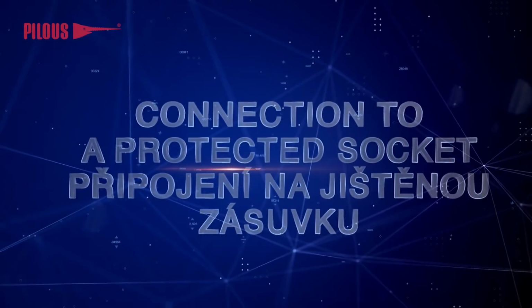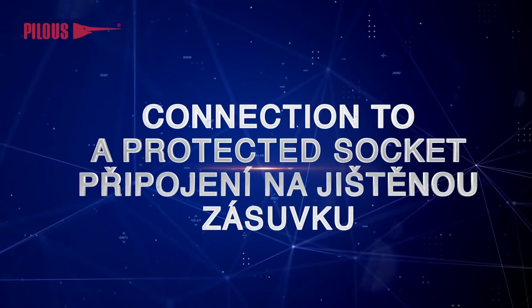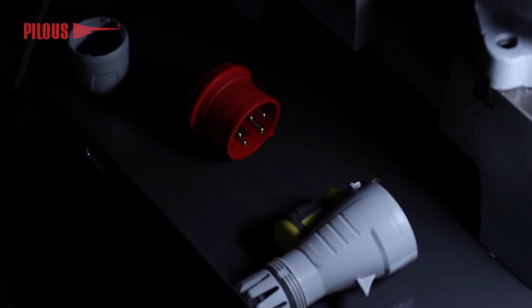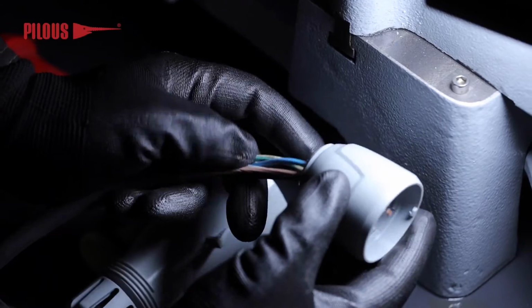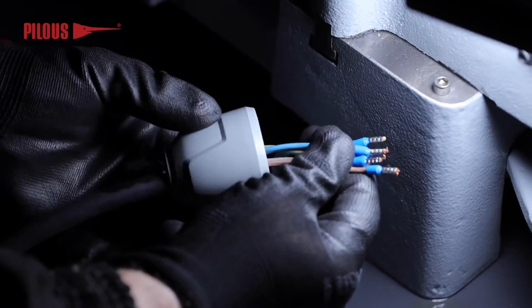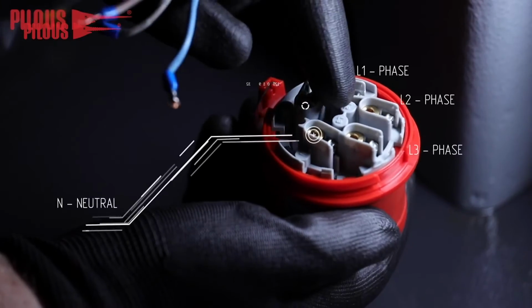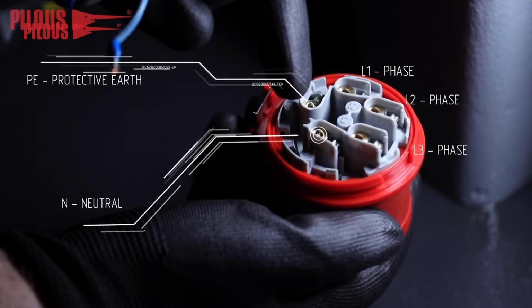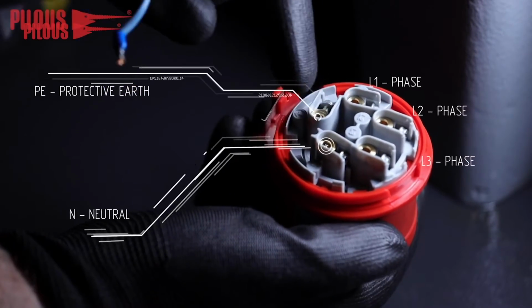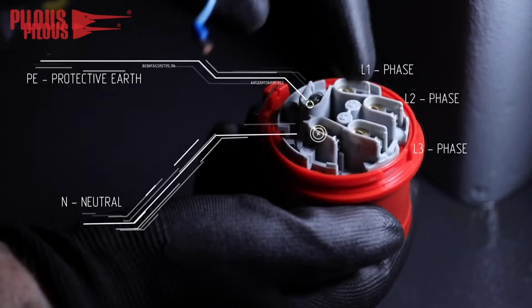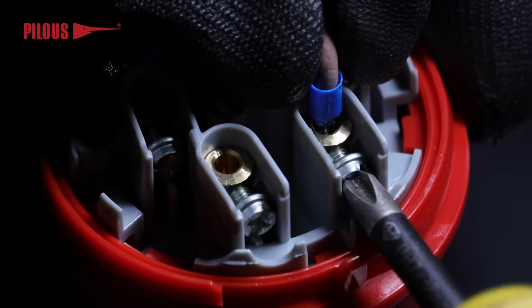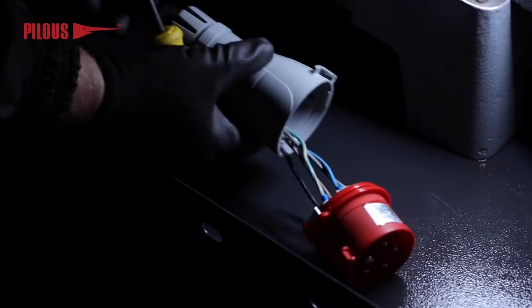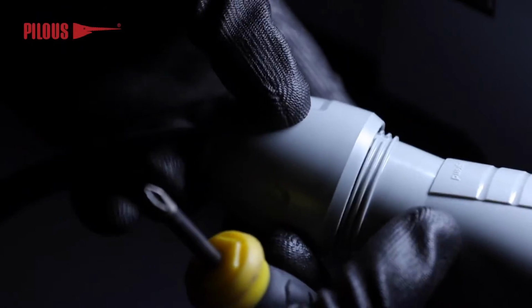There are 2 ways to connect the bandsaw to the mains. First, you can connect it to a protected 16 amp socket. Get a suitable 5-pin socket and a 400 volt 16 amps plug. Thread the cable through the plug and connect the wires. Improper connection of the neutral wire or protective wire can damage the electrical equipment of the machine and cause an electric shock.